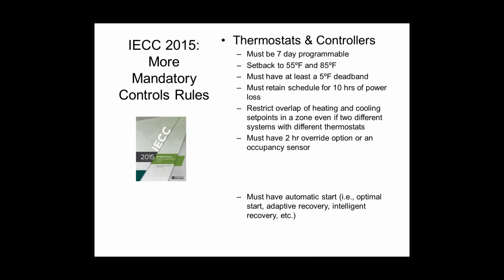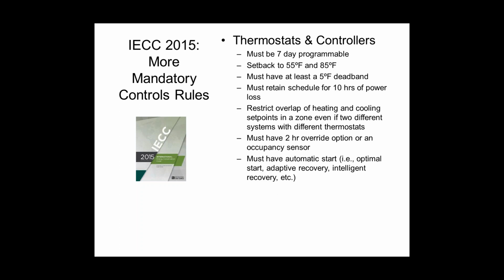That is also fine. You have to have intelligent start routines built into your thermostat or your DDC controls. There are lots of different names for those depending on the manufacturer of the stat, but they all work basically the same way. So if you tell the thermostat you're going to occupy your building at 8 a.m. tomorrow morning, normally someone would configure the stat and program it to turn on at 6 or 7 in the morning. Well, now you don't do that. You actually program the stat for 8 a.m.